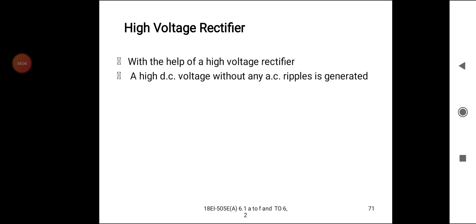The X-ray tube consists of a cathode. The cathode is given the high voltage DC signal from the rectifier. The heater filament is heated, which generates high-speed electrons. You can see the electron beam in the figure. The electrons travel at very high speed and are targeted onto the target material, a high melting point material like molybdenum or tungsten. There is a sudden stoppage of the electrons, and their kinetic energy is converted, producing X radiations or X-rays.